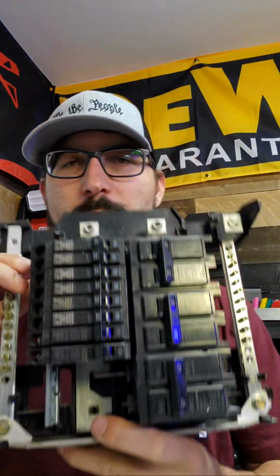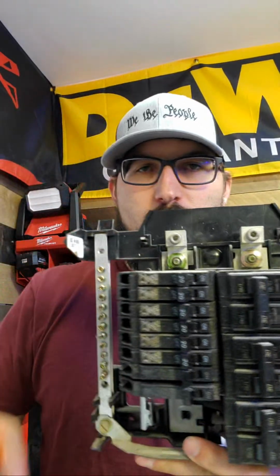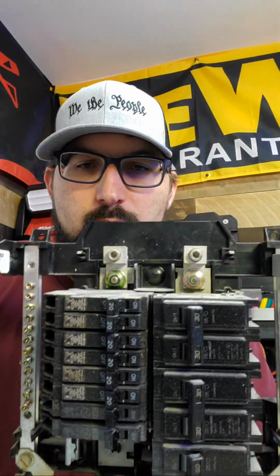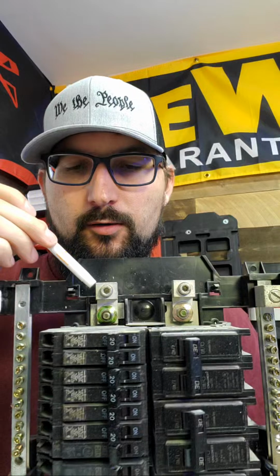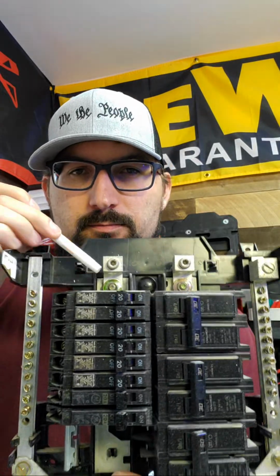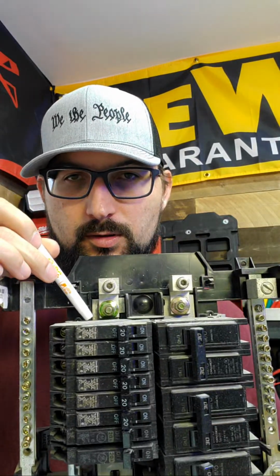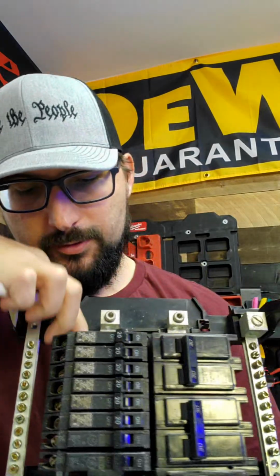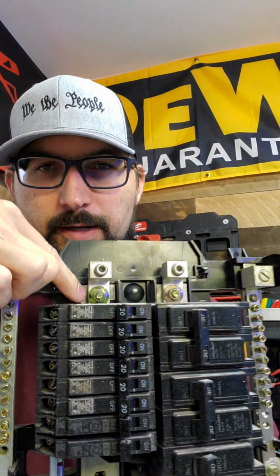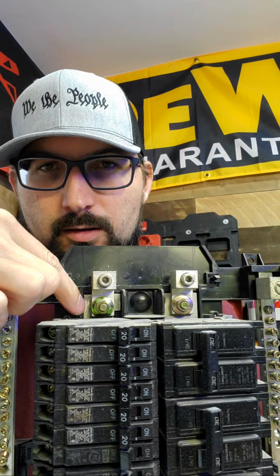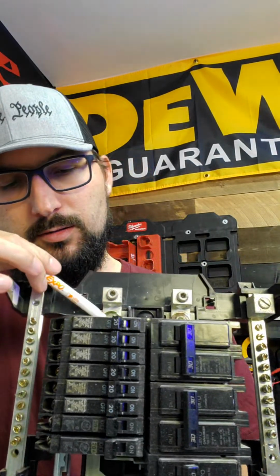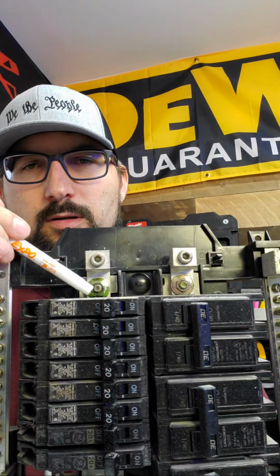All right, so if we're to do a ductor test here, we could go from this lug to this bus bar on the back there. And that would tell us if this nut was loose or not.